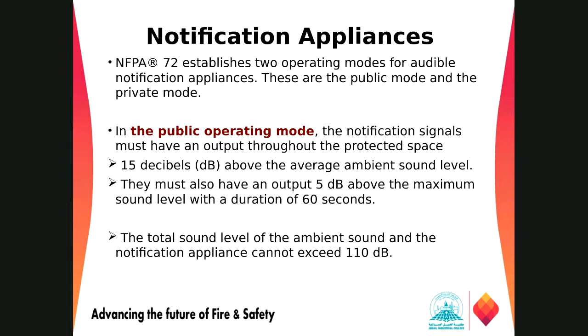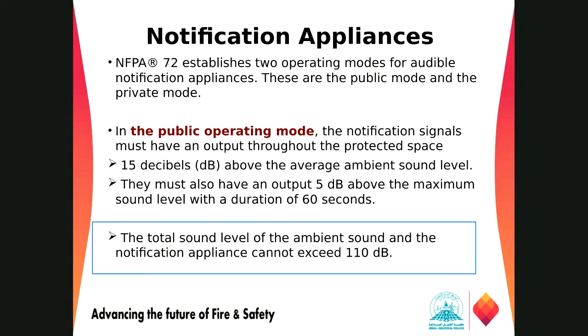And the total of ambient sound level and notification sound cannot exceed 110 dB, because 110 dB is the threshold limit. After that, if you are exposed to the sound, it will put more pressure on our ear, and it might give some problems inside our eardrum from time to time.